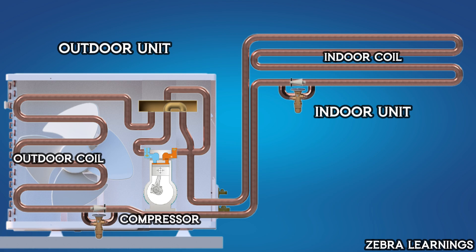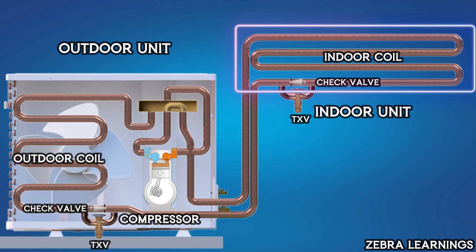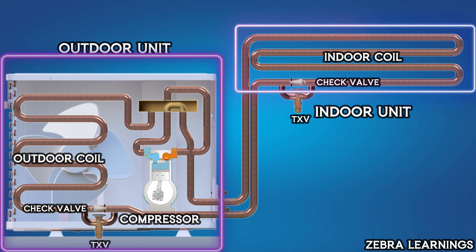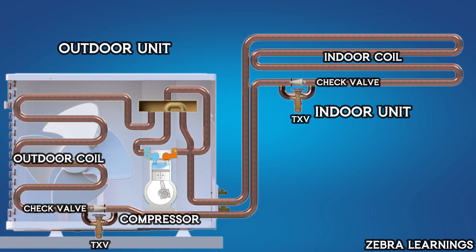But in addition to these, a heat pump has two extra check valves or non-return valves and two expansion valves. One expansion valve and one check valve are located in the indoor unit while the other set is in the outdoor unit. Additionally, the system includes a four-way reversing valve with two inlets and two outlets.